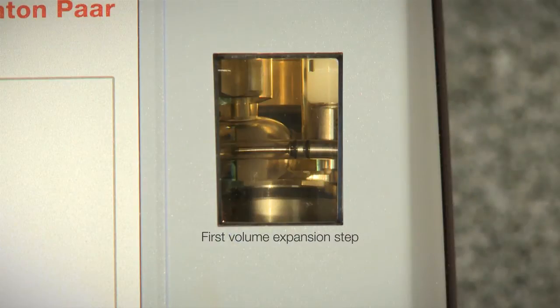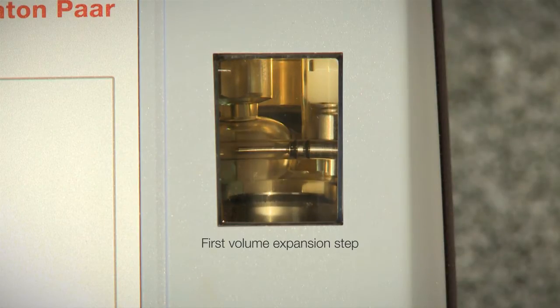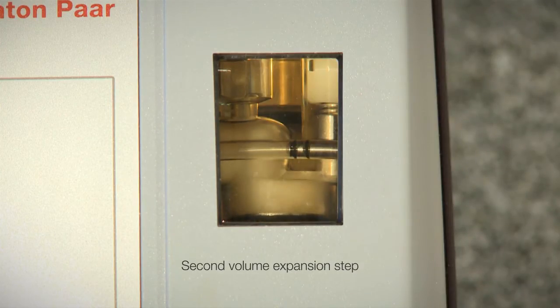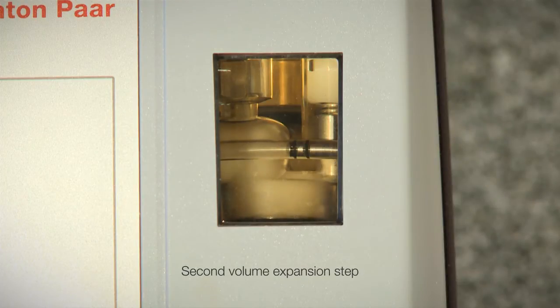After that, the CO2 measuring chamber is closed. The piston moves down and expands the volume for the first time. The pressure and temperature are measured. Then the piston moves down further and the volume is expanded a second time. The pressure and temperature are measured once again.